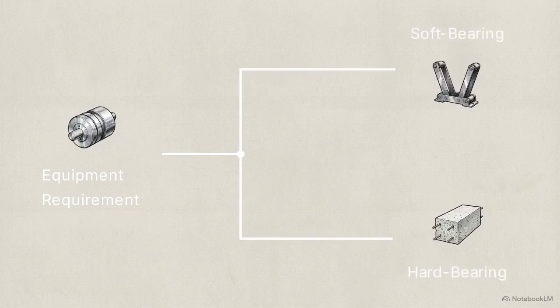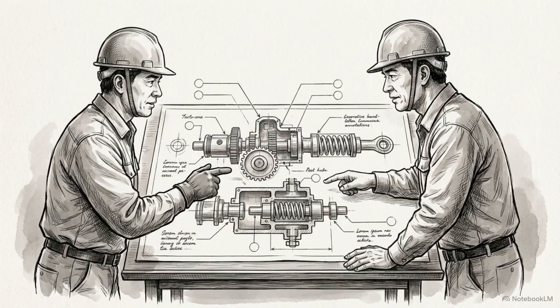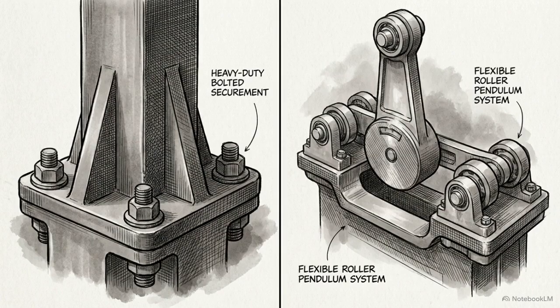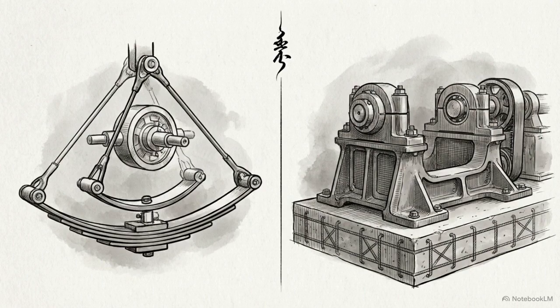To fix this, manufacturers rely on rotor balancing machines to detect and correct those weight irregularities. But when you go to equip a facility, you are forced to make a choice between two different systems. Engineers have to pick a side in a mechanical debate. To eliminate vibration, you must choose either absolute rigidity or yielding flexibility. The balancing industry is split down the middle by these two approaches, soft bearing and hard bearing balancing machines.